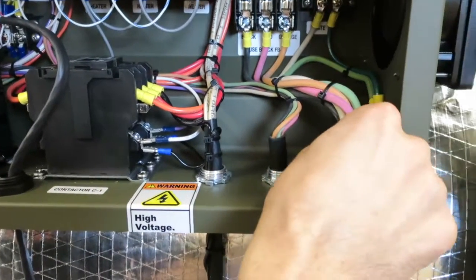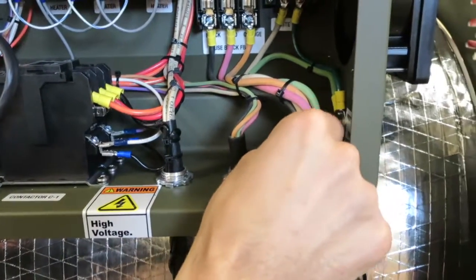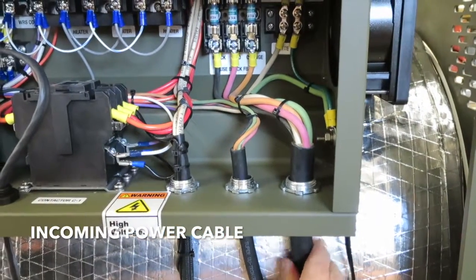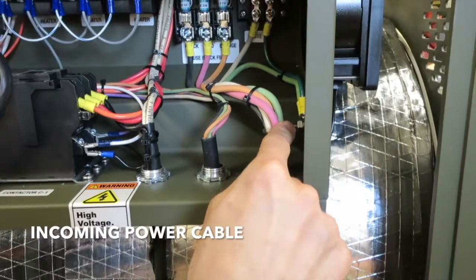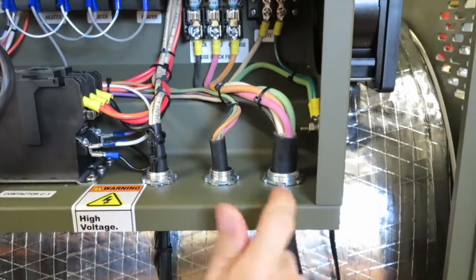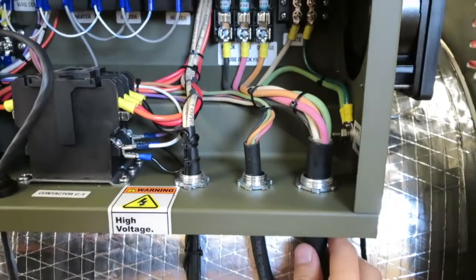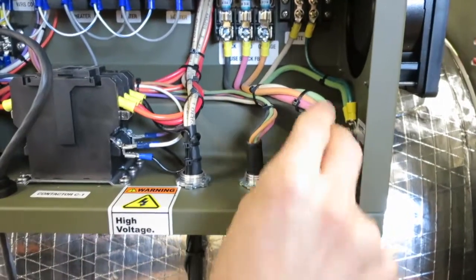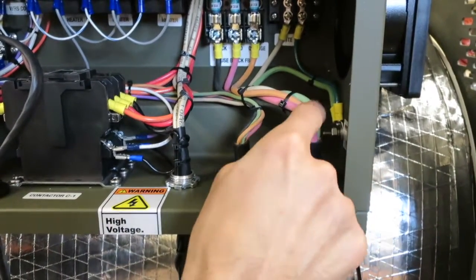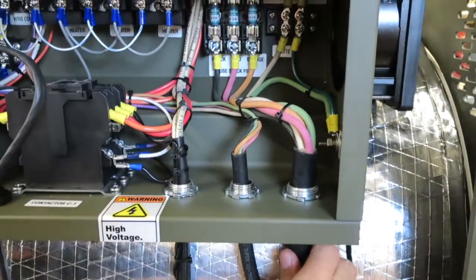Finally, on the cables, I have this large cable, which is the input power to the sterilizer main unit. So again, it's 3-phase 208, very high voltage in this area. You want to be very careful. Also have a ground and a neutral, so it's a 5-wire incoming power.